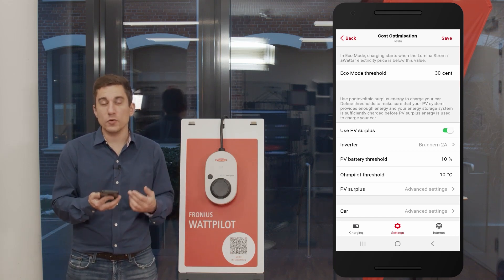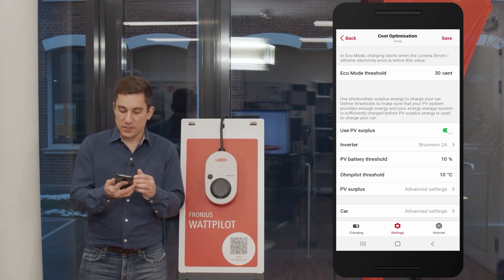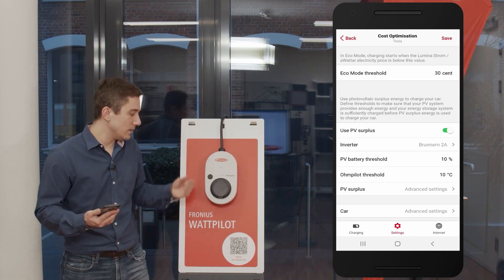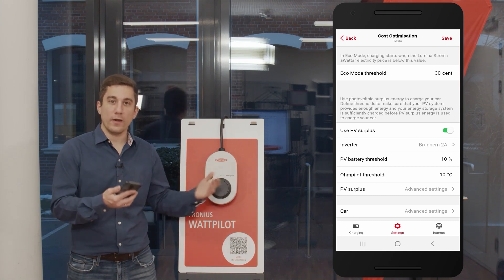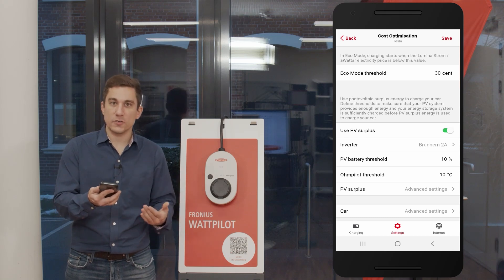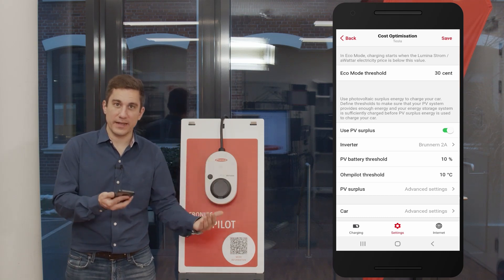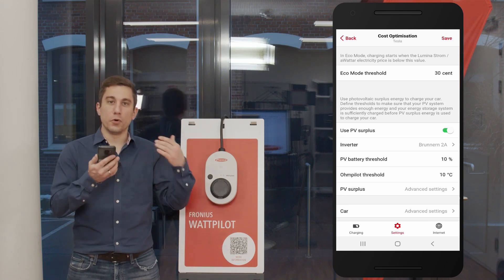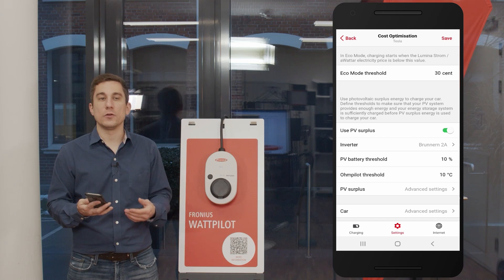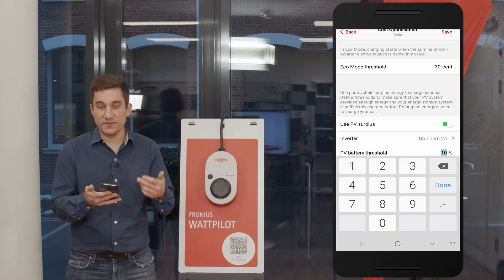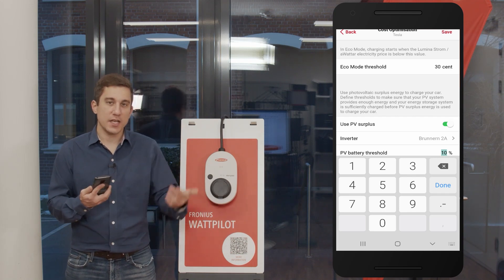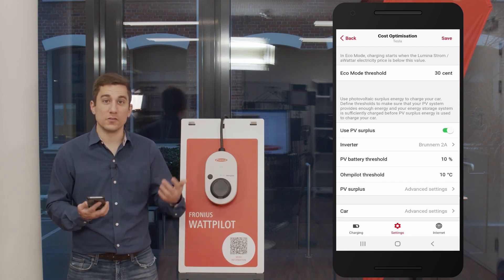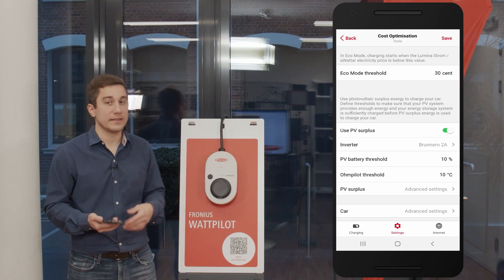The second threshold is the Ohmpilot value. At 10 degrees Celsius, as soon as that temperature is reached in the hot water boiler, the Wattpilot will get the energy. So whenever you want to operate the Wattpilot, both the PV battery threshold and the Ohmpilot threshold need to be fulfilled by the Fronius system. When you set these values relatively low — 10% SoC and 10°C — both will be met most of the time, so the Wattpilot gets energy first.